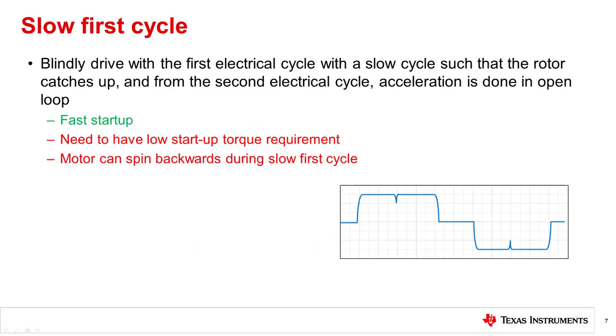Slow first cycle is similar to Align except that instead of applying a stationary Align vector, the system slowly moves the Align vector for one electrical cycle throughout the alignment process. One main advantage of this method is the ability to achieve faster startup since not only will the motor position be determined, the rotor will already be moving when the system begins acceleration. However, the motor being driven needs to have a low startup torque requirement in order for the rotor to properly catch up with the rotating vector, and the technique still doesn't eliminate the possibility of the motor spinning backwards.